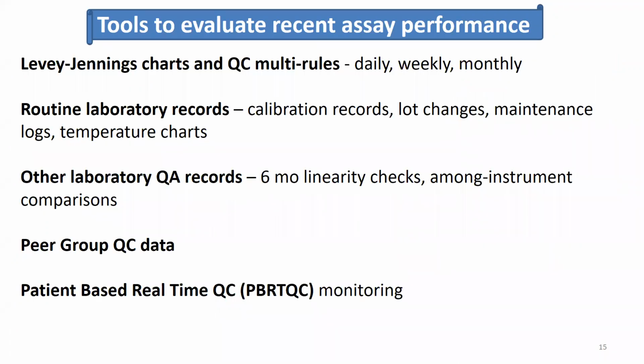The good news is that we do have tools to evaluate recent assay performance. Of course, we can examine the Levey-Jennings charts and take a look at our QC multi-rule performance. We can examine our daily, weekly, and monthly QC statistics. We can check routine laboratory records, so our calibration records, our lot change records, our maintenance logs, and temperature charts to see if there might be any deviations that explain our QC alert.